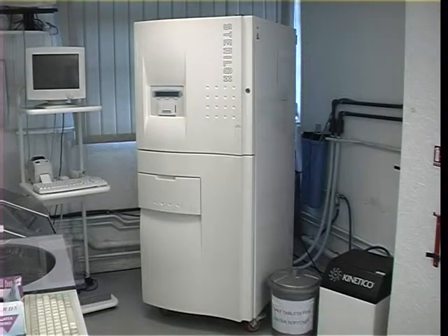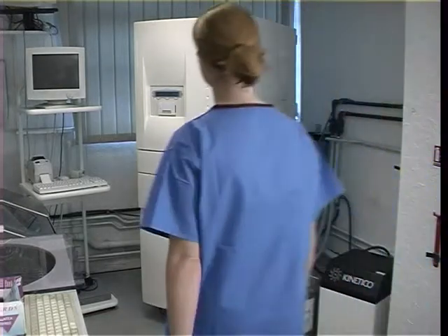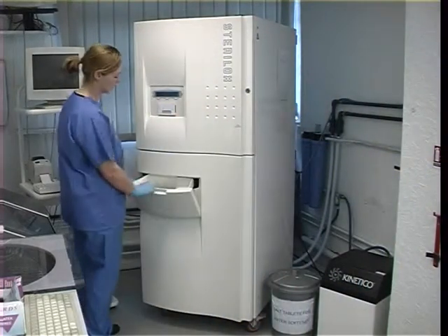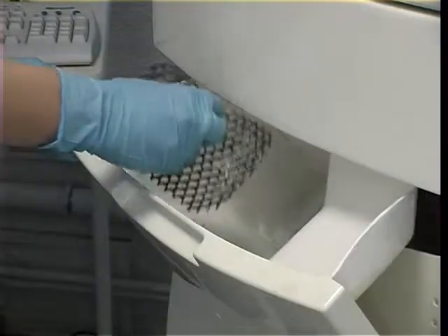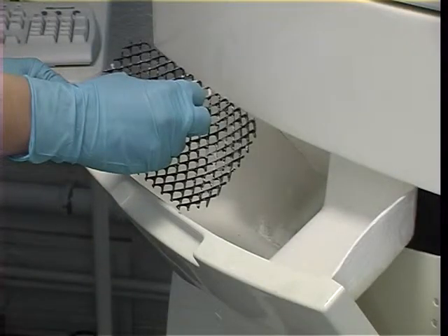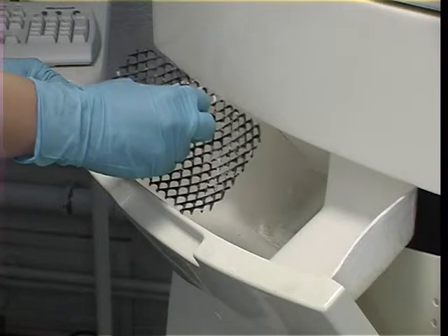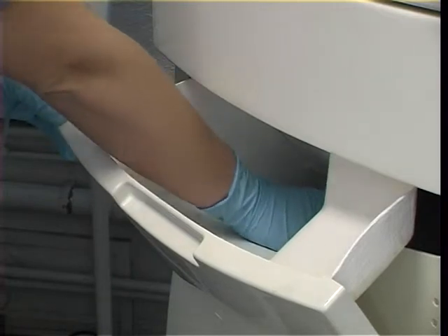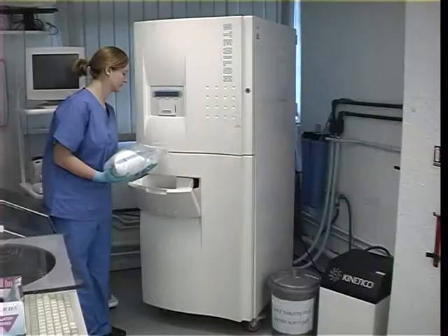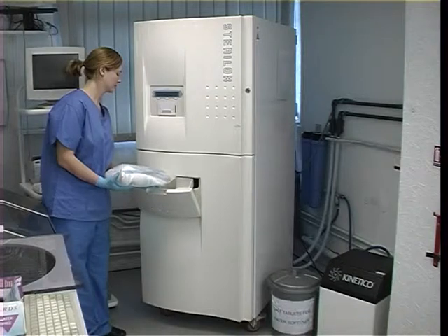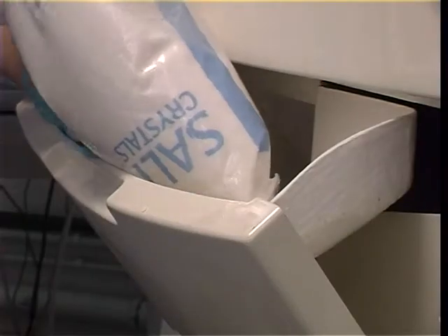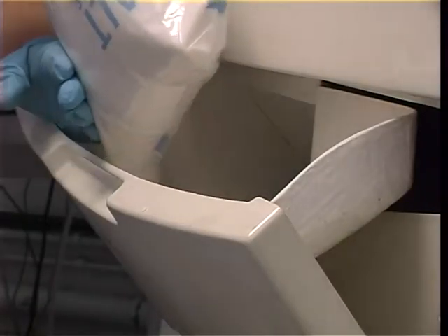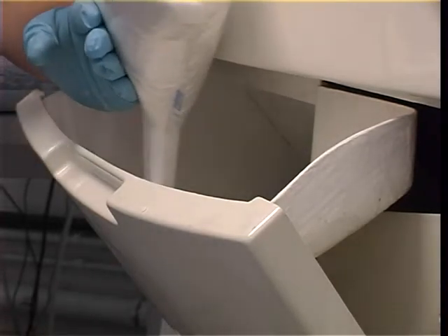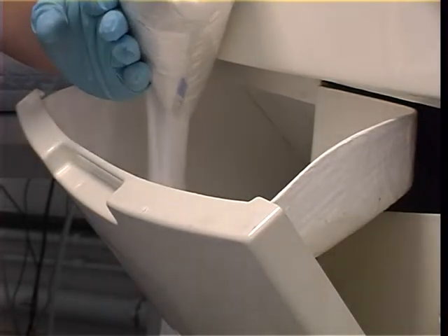When the 2501 alarm sounds and the message on the display screen tells you that the generator needs salt added, firstly, always check that the salt grill is clean and clear to allow unobstructed flow of salt into the tank. You should then add 2 6-kilogram bags of salt that is supplied by Sterilox Technologies for this purpose. The salt is granular and free-flowing. Open the bag carefully and pour the salt into the chute, taking care not to spill salt onto the floor. Do not cancel the alarm on the generator without completing the task required.